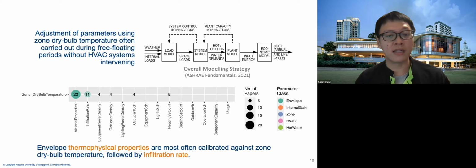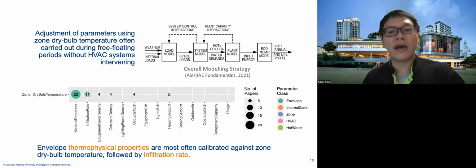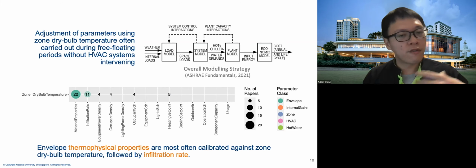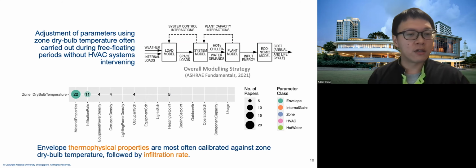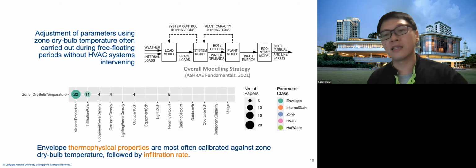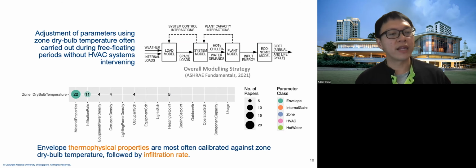Decoupling the model makes sense because it significantly reduces the number of parameters you need to think about when conducting the calibration. Additionally, from our initial review, we found that material properties as well as infiltration rate are often the parameters identified when calibrating against dry bulb temperature. So we also measured the thermophysical properties of the building envelope using RTD and heat flux sensors, and tried to derive infiltration rate using tracer gas tests.